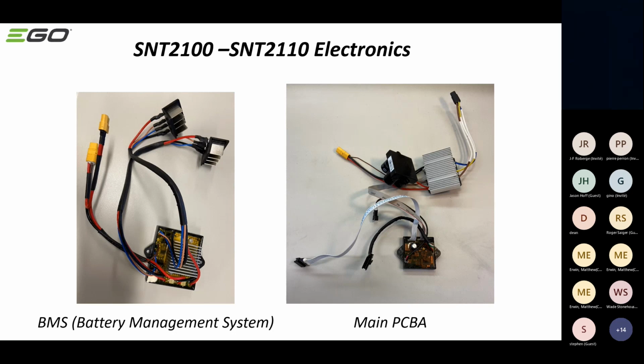We do not offer any of those individual components for each PCBA separately. So if anything goes wrong, like you need a new fuse for the BMS, you would just replace the whole unit. Same likewise with the main PCBA - if that checks bad and needs to be replaced, this is what you would order, everything that you see in this picture.